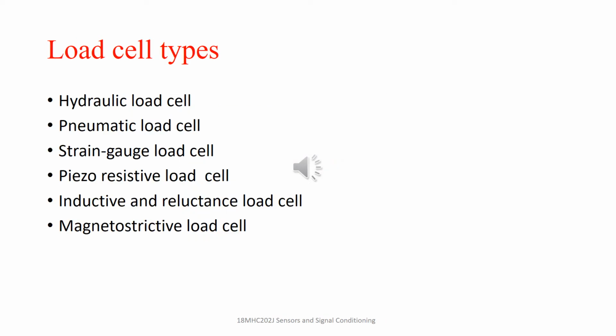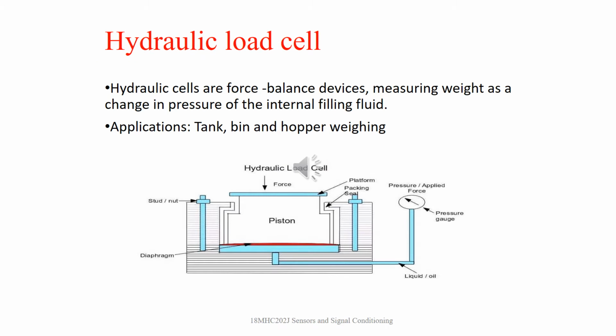Load cell designs can be distinguished according to the type of output signal generated, that is pneumatic, hydraulic or electric, or according to the way they detect the weight, that is either by bending, shear, compression, tension, etc. This type is the hydraulic load cell. These are force balancing devices which measure weight as a change in pressure of internal filling fluid.